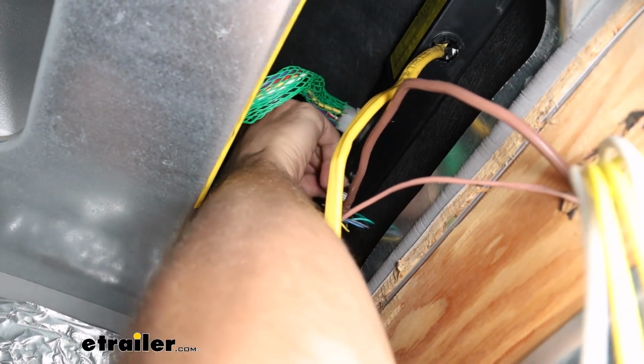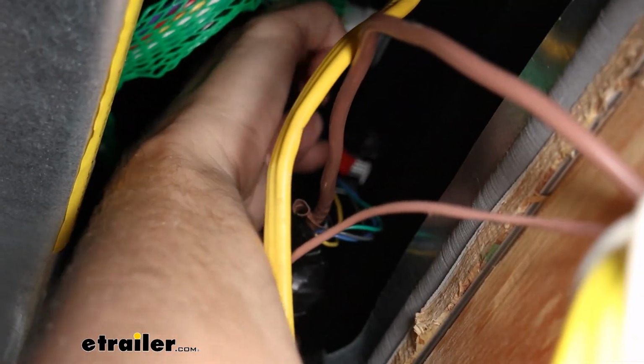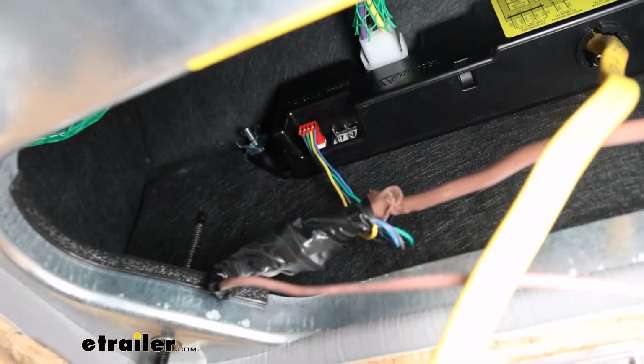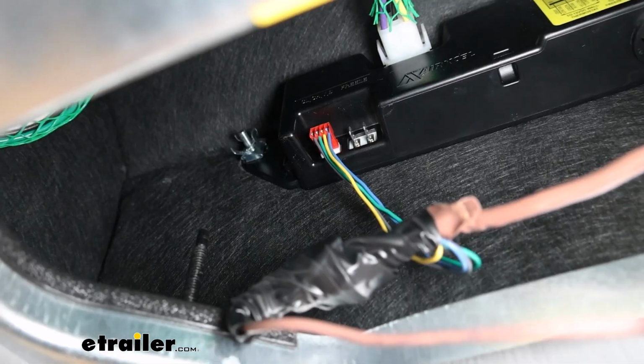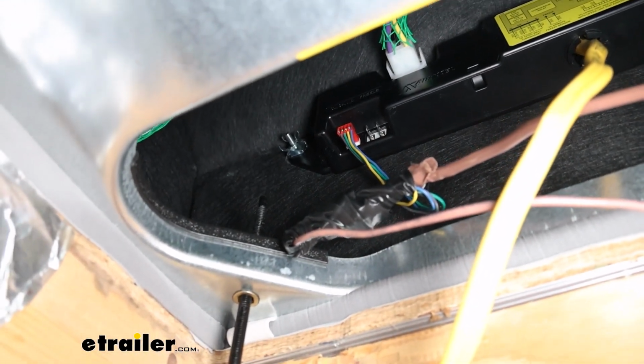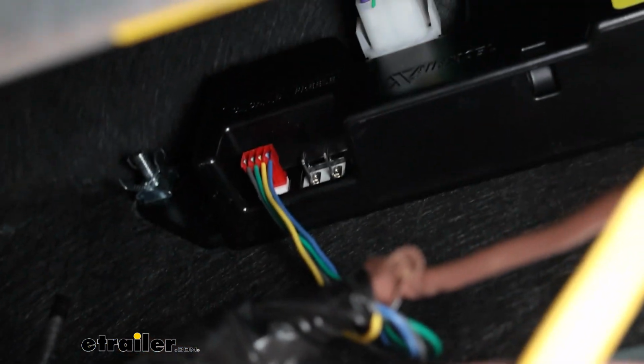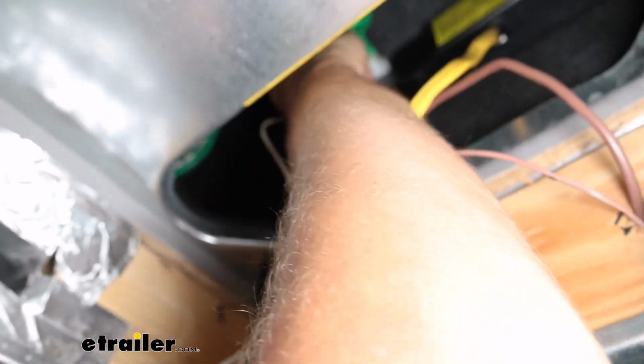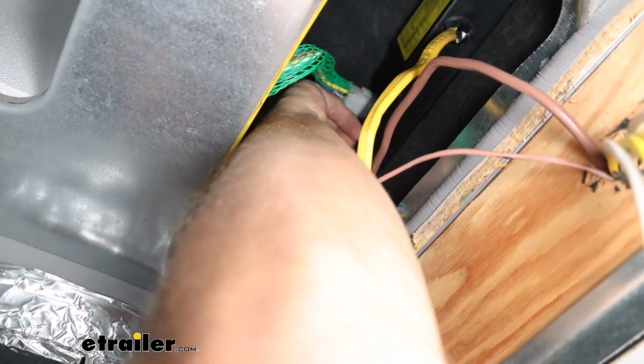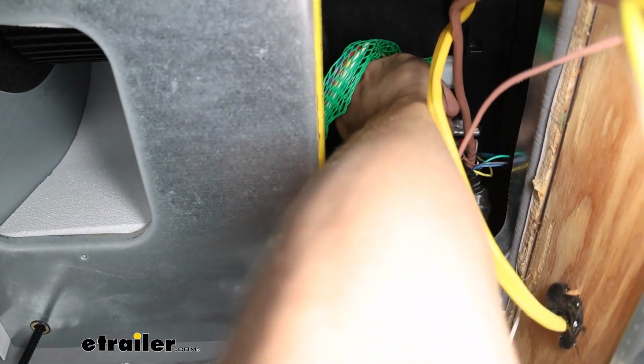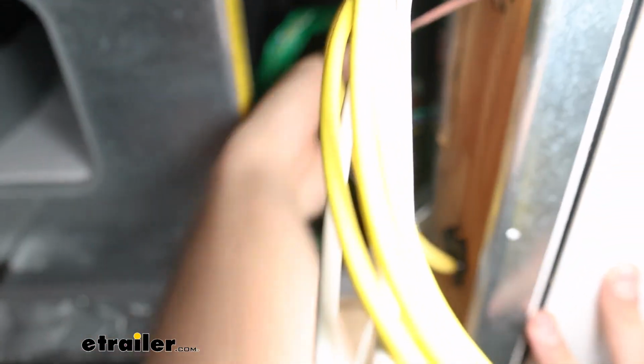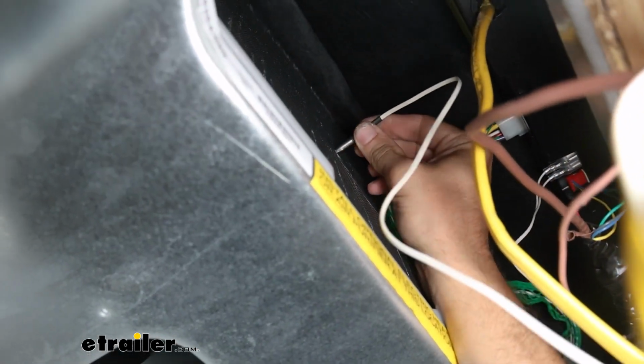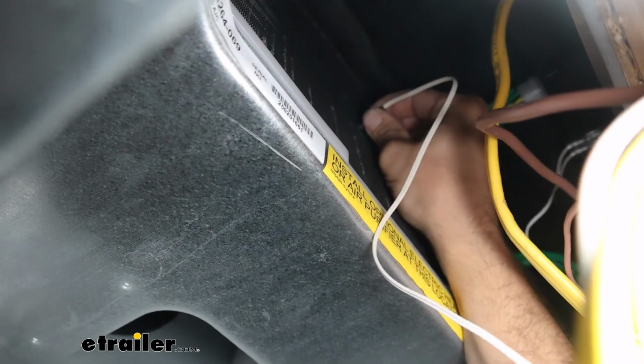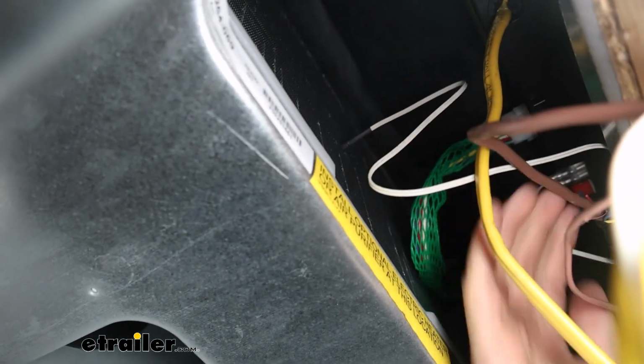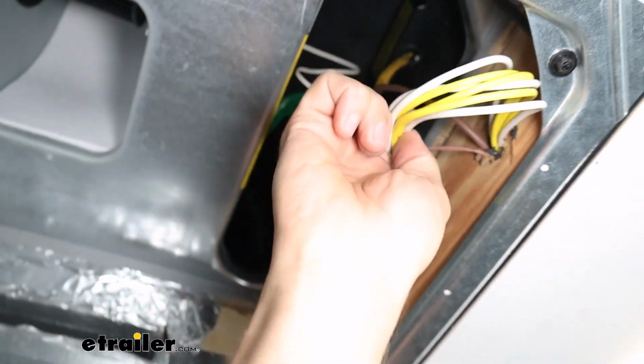Up here we've got 4 prongs on this white connector. We're going to hook in our little red connector, and then grab that temperature probe, or freeze sensor. The spade terminals on that don't matter for polarity, so we'll just pop those on and put it up about halfway, around the center. Just push it in, and then we can tuck our wiring up out of the way.